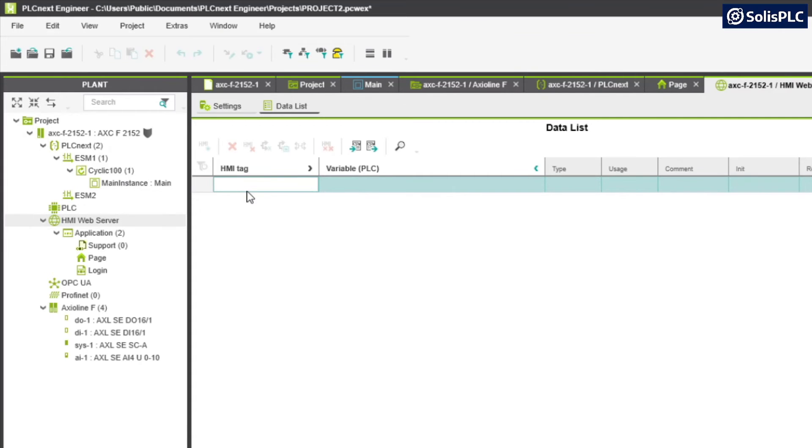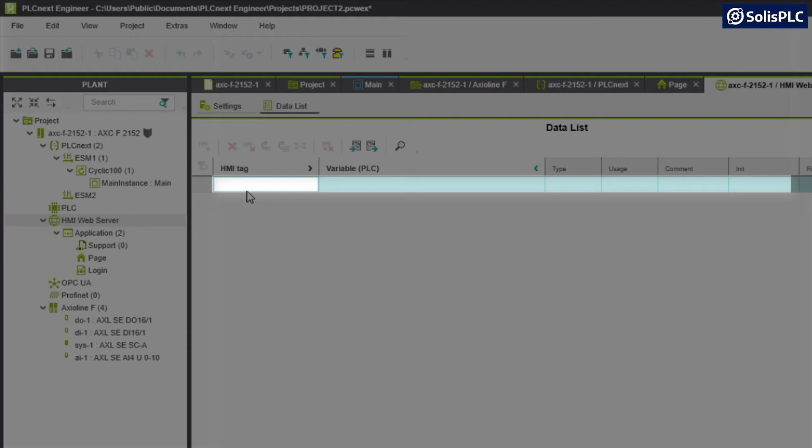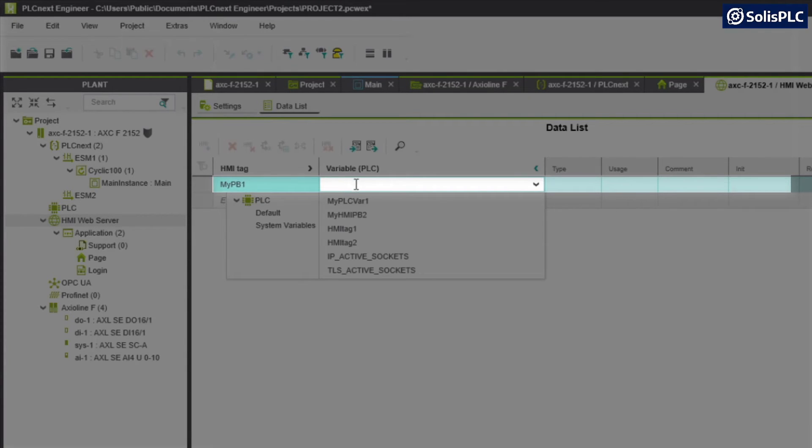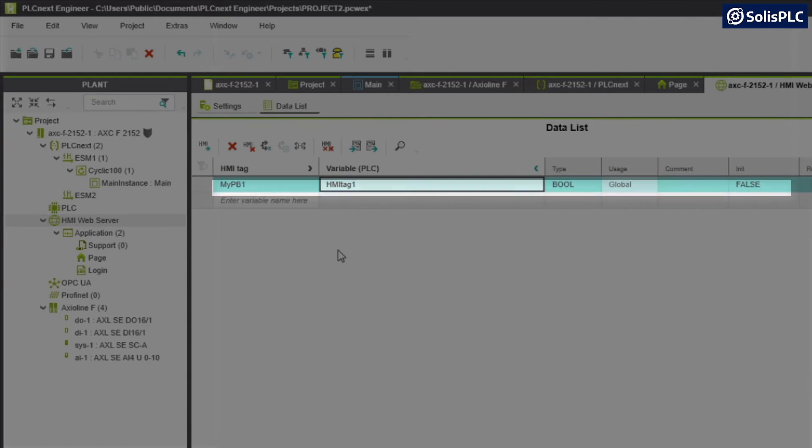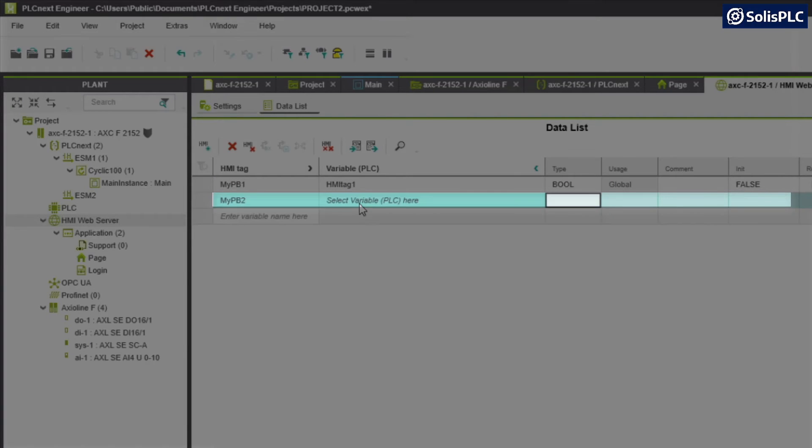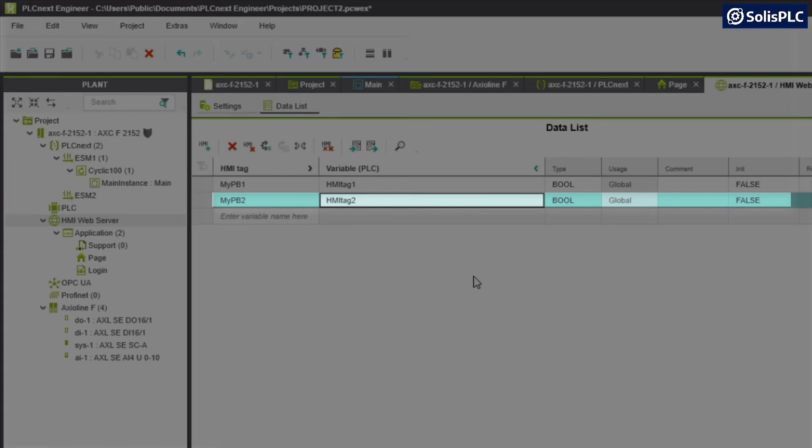What I'm going to do here is I'm going to create my push button myPB1, and here you'll notice that I can specify the variable on the PLC side that this represents. In my case that's going to be HMI tag 1. Here I'm going to create myPB2 and this is going to be HMI tag 2.